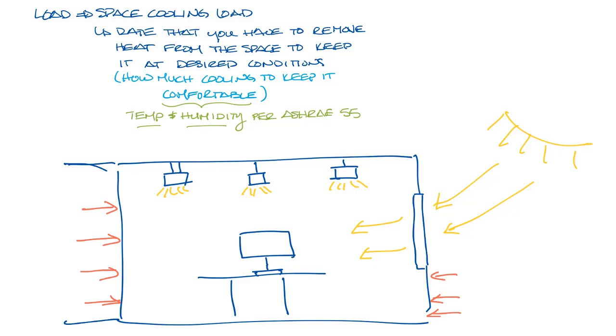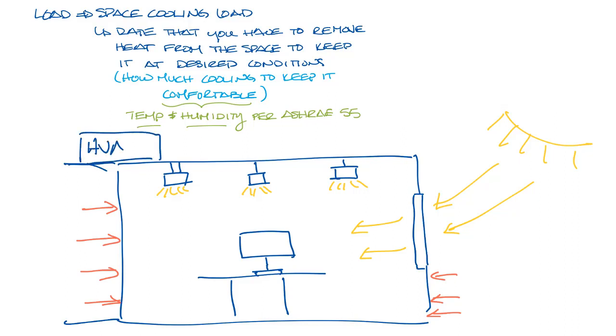Also, people have a heat load. People are approximately the same as a 100-watt light bulb. And although you wouldn't see it in the space, the ventilation air and HVAC equipment itself can add heat and humidity to the total building HVAC system.